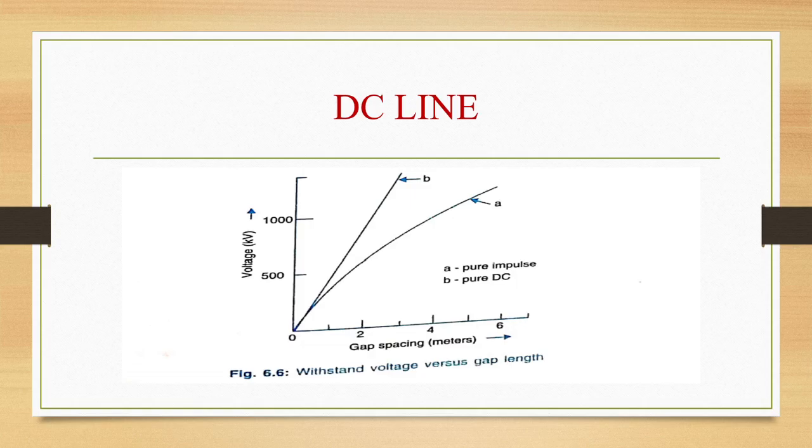Major problem with DC insulators is that the accumulation of contamination through the direct voltage stresses is higher than with AC lines. Collection of dirt particles is also less uniform than with AC. Providing collector rings close to the ends of the string helps in making the field distribution more uniform and reducing the accumulation of contamination. Insulators will be cleaned by heavy rain while the fog or dew, which makes the dirt conductive without removing it, can result in flashover.